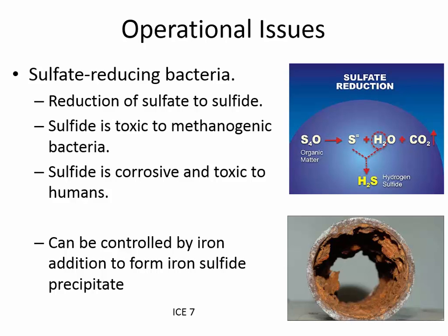Sometimes we have hydrogen sulfide smell here in this building. Like when you walk in the doors, you can sometimes have a smell. You maybe think it's natural gas, but what they've tested several times and found out is that there's drains in the engineering building with stagnant water, and underneath that, whatever scum is in that drain is being broken down. Sometimes they'll see hydrogen sulfide accumulation in sewers that have really low flow rates and the wastewater isn't mixed.